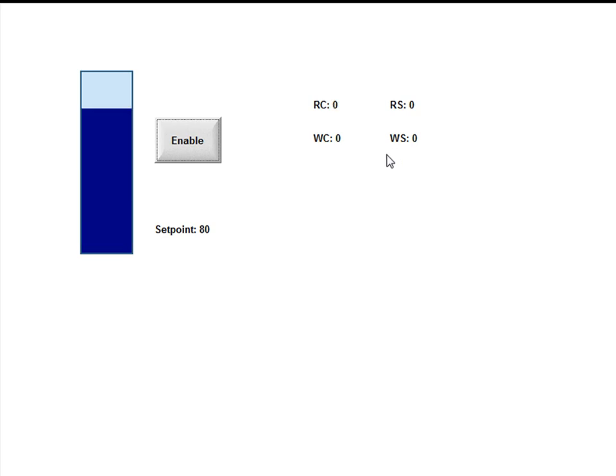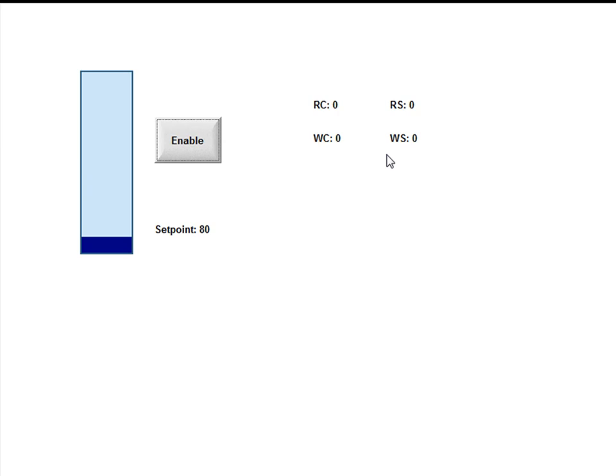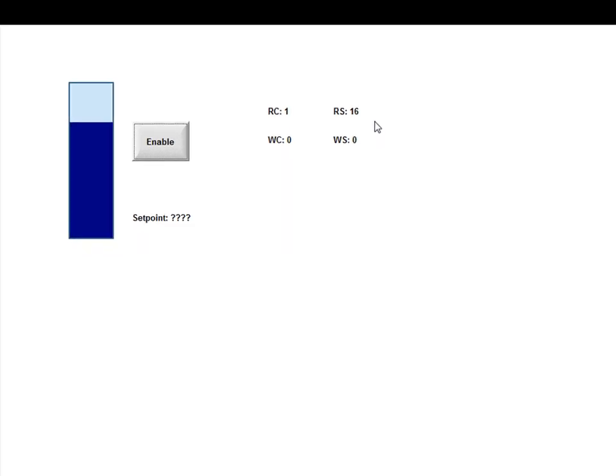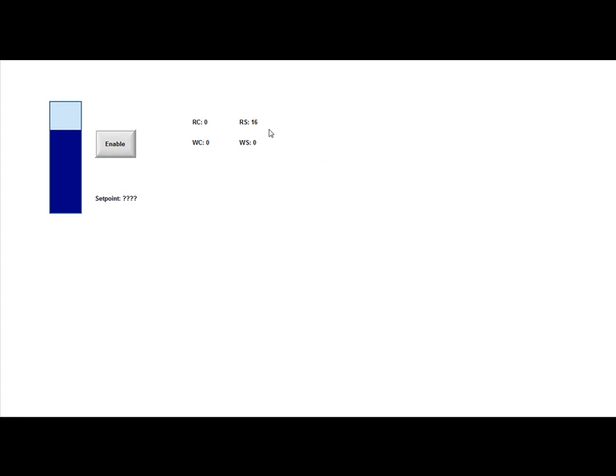Now I'm going to pull the Ethernet cable off of the PLC. And what you will see is question marks happen in the set point, and now we'll see a read status of 16. If you go look that up in the manual, the MODTCP manual, it will tell you what type of error code that is.